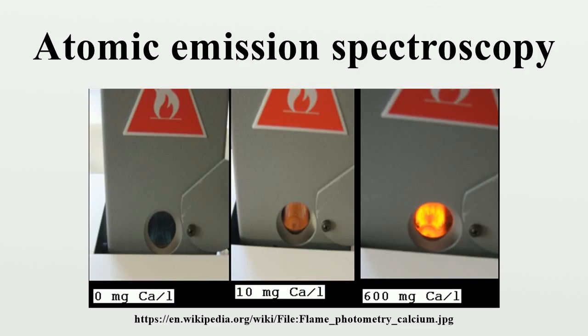The excited atoms subsequently emit light when they return to the ground electronic state. Each element emits light at a characteristic wavelength, which is dispersed by a grating or prism and detected in the spectrometer. A frequent application of emission measurement with the flame is the regulation of alkali metals for pharmaceutical analytics.